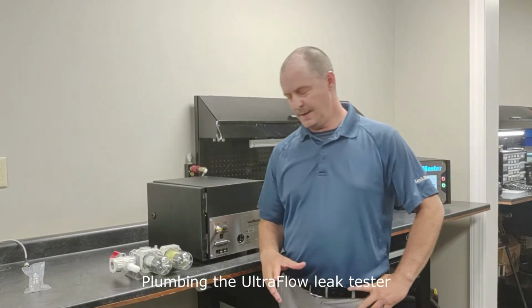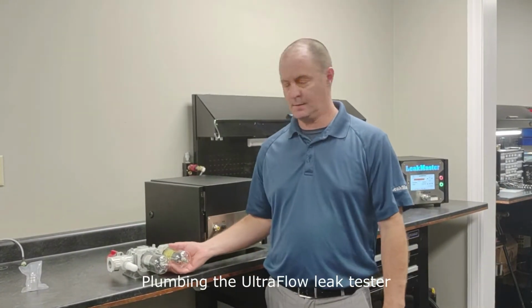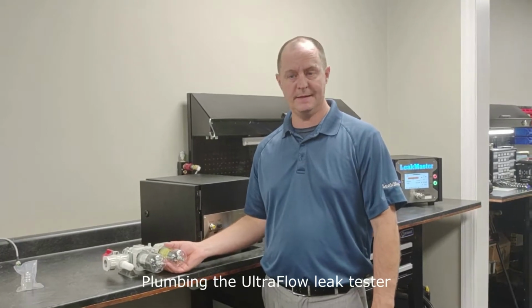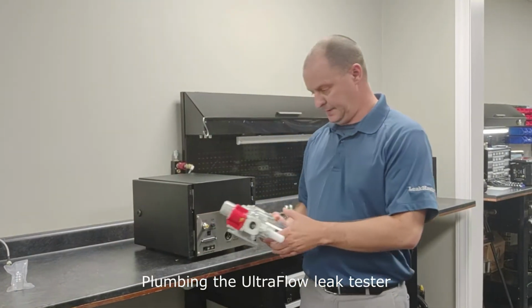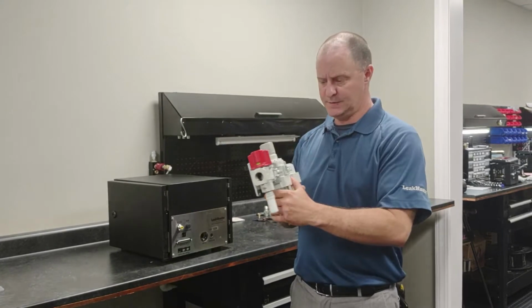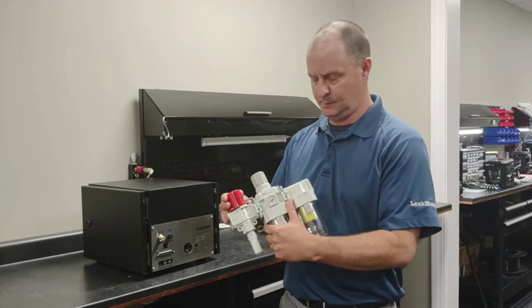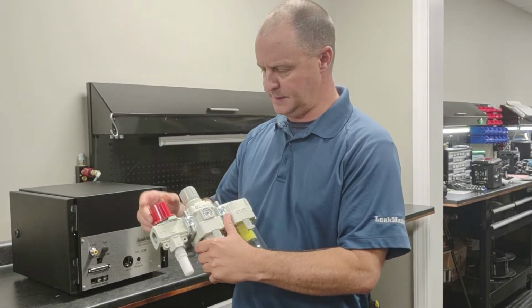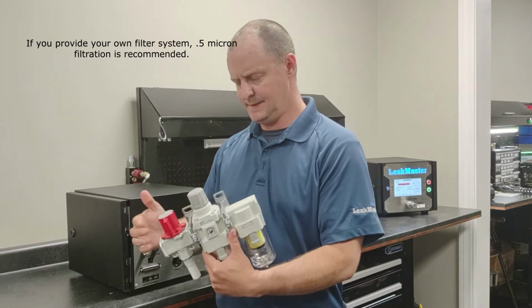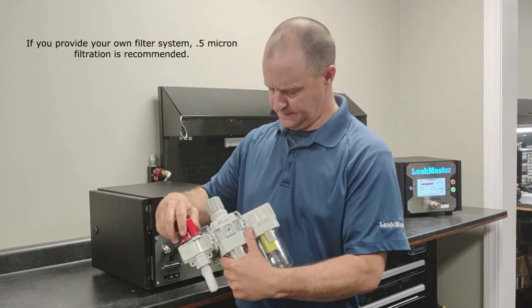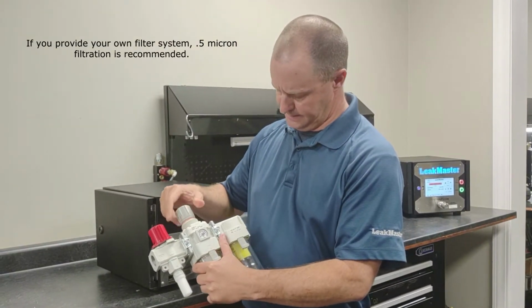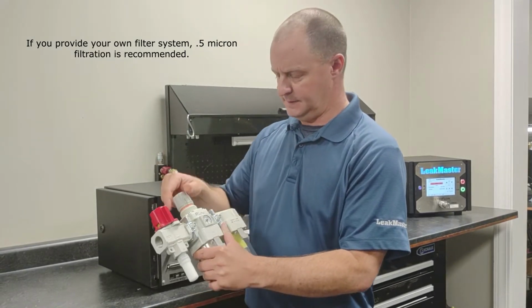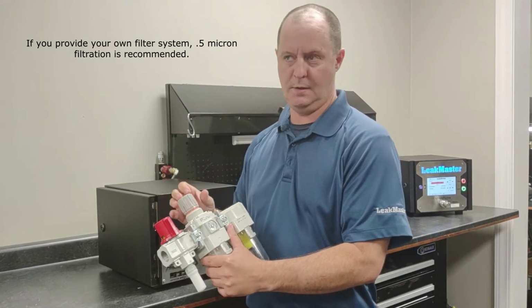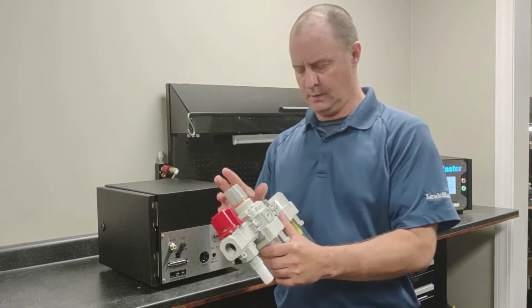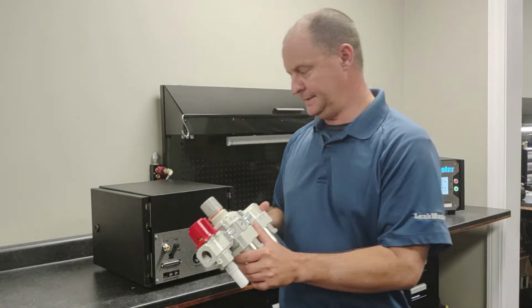Now that we have the unit unpackaged, the first thing we're going to do is start working on plumbing compressed air into the air supply for the unit. And we always recommend an air prep unit, which is going to provide clean, dry air to it. This is an option that we sell that's going to have a shutoff valve, a regulator, and then a coalescing filter. So this should clean any moisture or oil out of the air line that's coming into it.